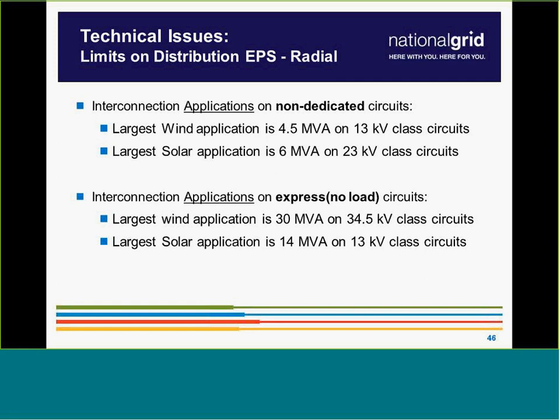So here's just a general guideline, I threw this slide in to explain this. For non-dedicated circuits, you can do maybe 4.5 megawatts on a 13 kV class feeder. For solar, you can do 6 megawatts on a 23 kV class feeder. The key thing is which feeder you're trying to connect to, and if you're closer to the substation, that's probably better. Now if you're doing something on an express feeder with pretty much no load, I've seen up to 30 megawatts MVA on a 34.5 kV class feeder. Also for solar, 14 megawatts on a 13 kV class feeder.